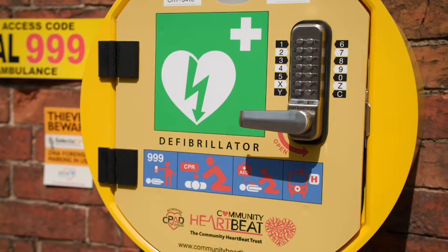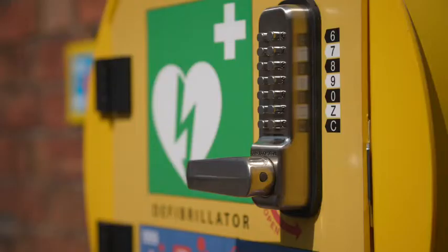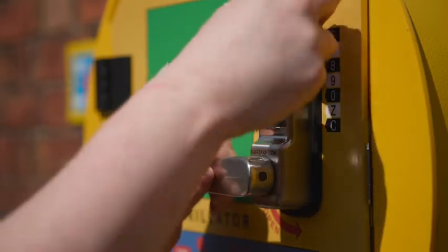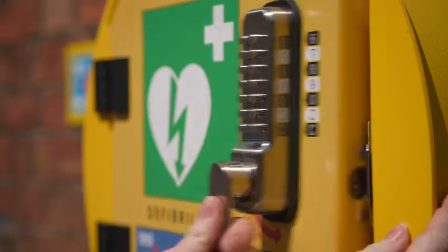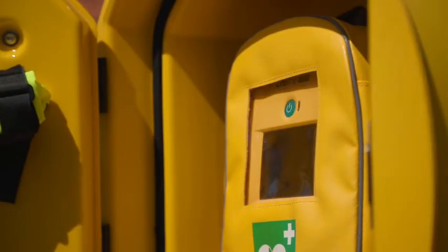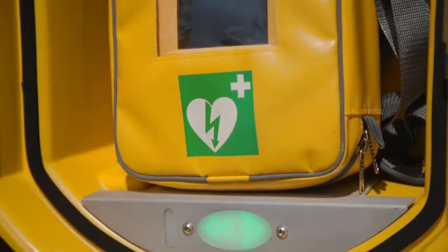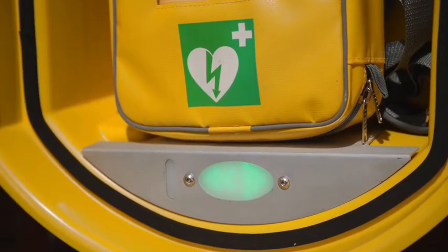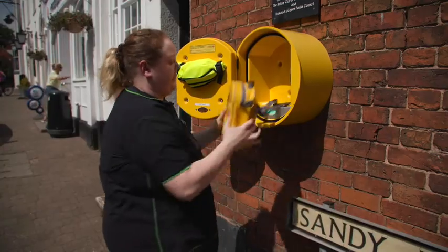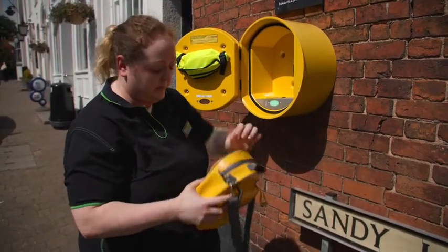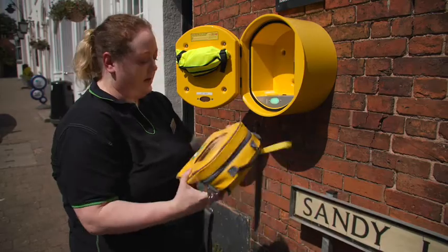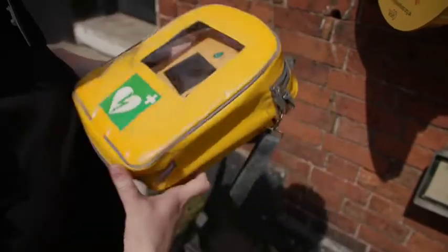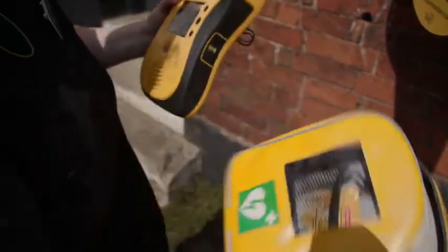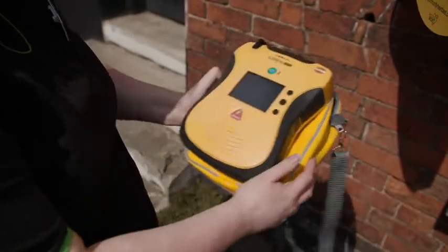Checks should include looking at the cabinet to ensure it is not damaged in any way. Looking at the lock, if one is fitted, to ensure this is working. The more often you open the cabinet, the better the lock works. Looking at any electricity indicator light to ensure power is being supplied. Look at the defibrillator. Make sure there is no water in the cabinet or on the defibrillator. Take the defibrillator out of its case and look at the general condition. Are there any signs of damage?